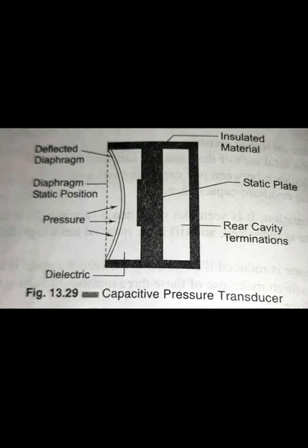This diaphragm is used as one plate of the variable capacitor, and its distance from the stationary plate to the left is determined by the pressure applied to the unit. This determines the capacitance of the two plates. The monitor indicates the pressure in equivalent units of capacitance by measuring the capacitor reactance to the AC source voltage. That means the portion of the chamber to the left of the moving plate is isolated from the other side, where pressurized gas and vapor are introduced.